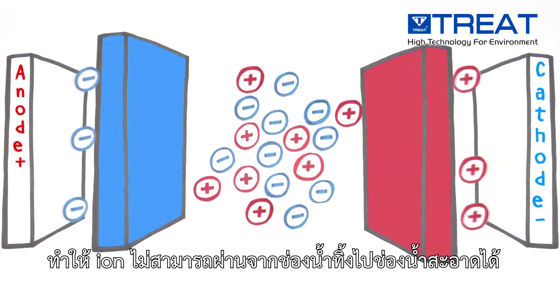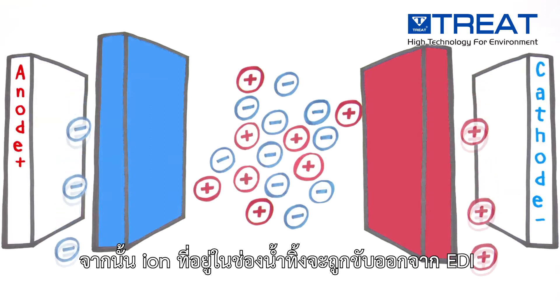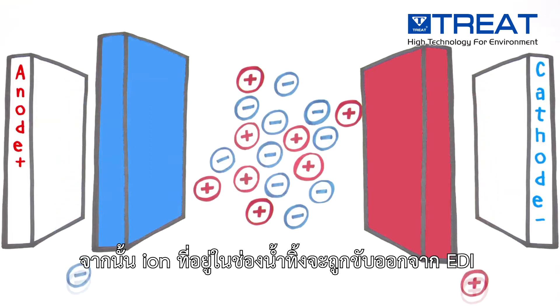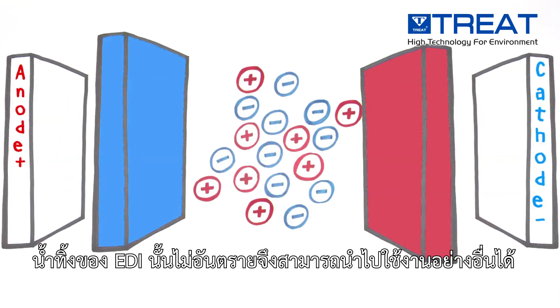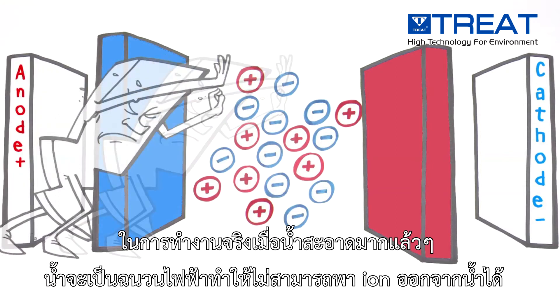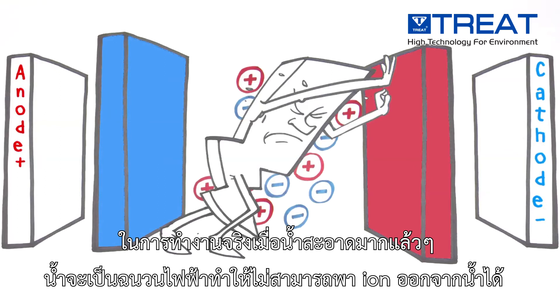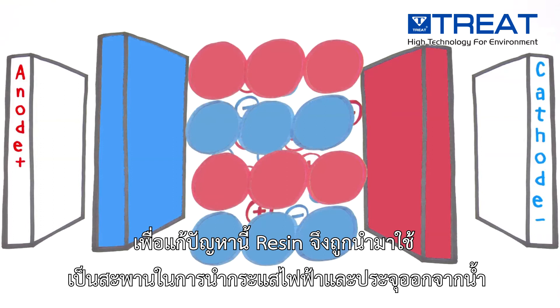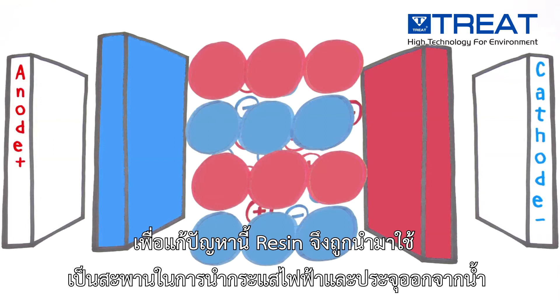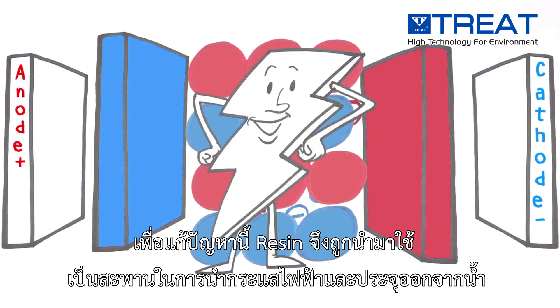The trapped ions are flushed out with the reject stream, which is then discarded, recycled, or processed further. However, low conductivity feed waters inhibit passage of the electric current that transports ions. That's where the resin comes in — it acts as a bridge to carry electric current and ions through the module.